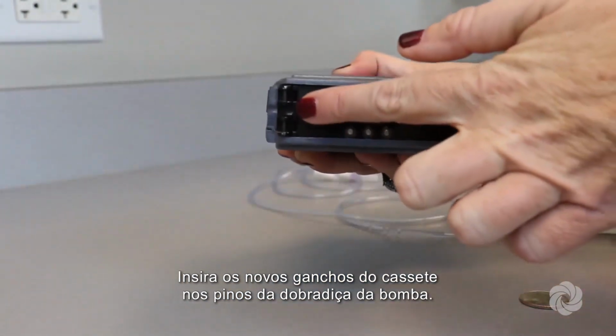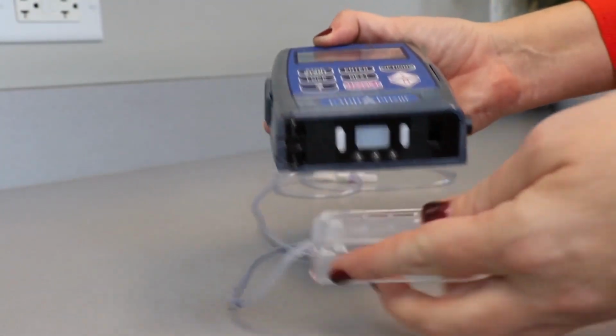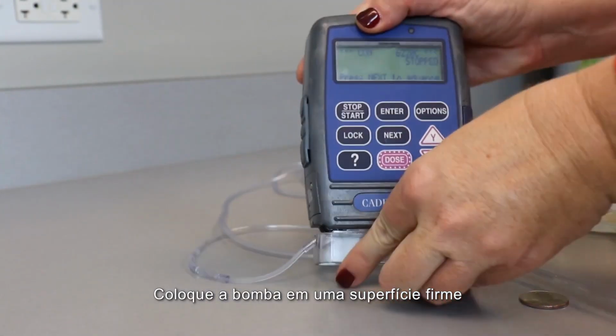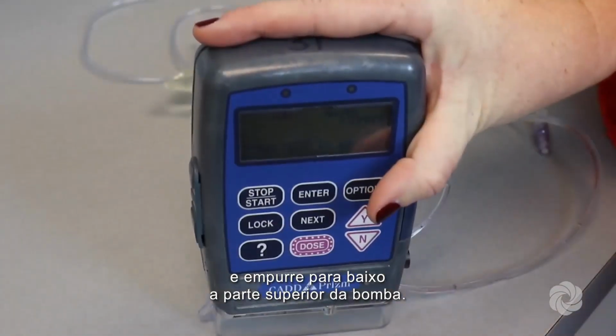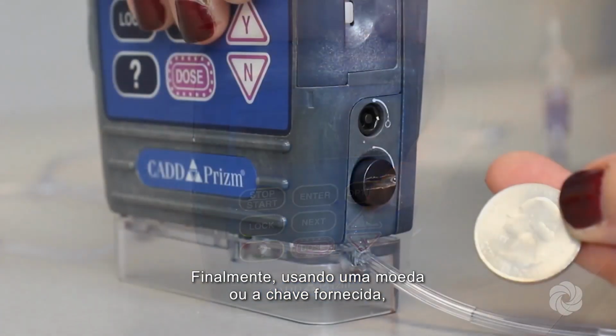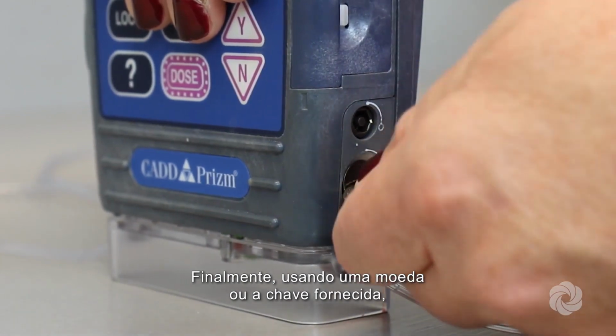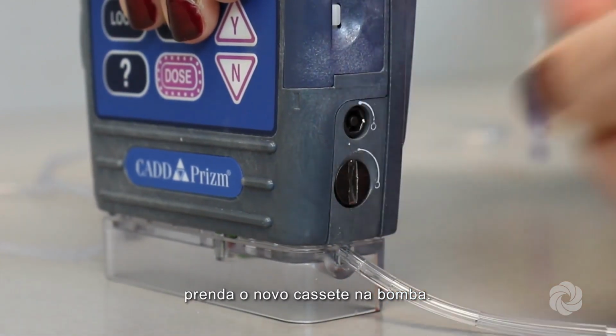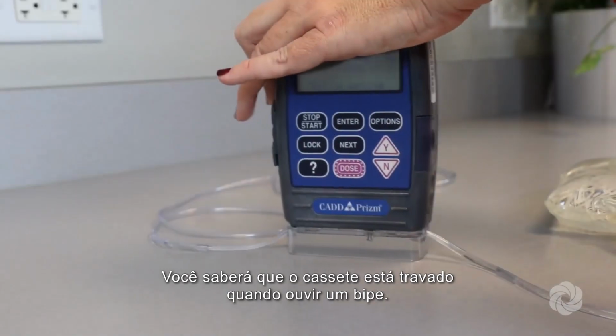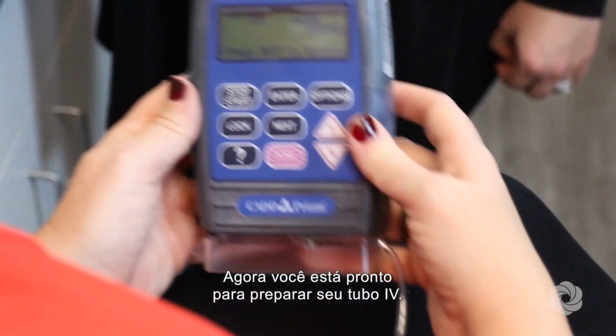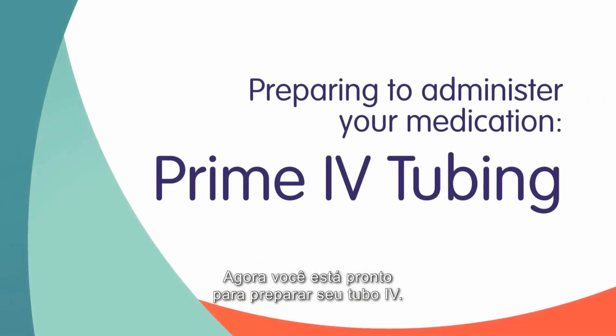Insert the new cassette hooks into the pump's hinge pins. Place the pump on a firm surface and push down on top of the pump. Finally, using a coin or the key provided, lock the new cassette to the pump. You will know the cassette is locked when you hear a beep. You are now ready to prime your IV tubing.